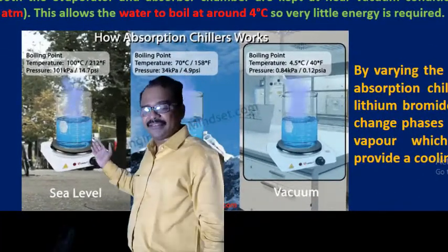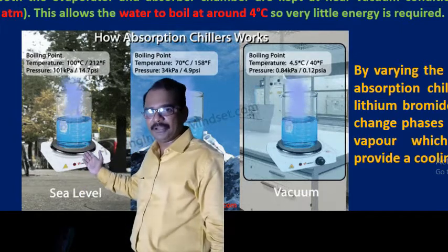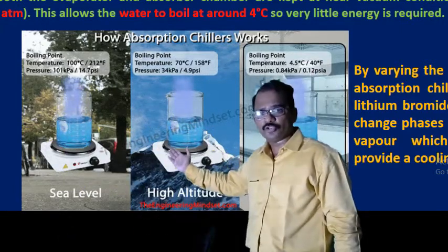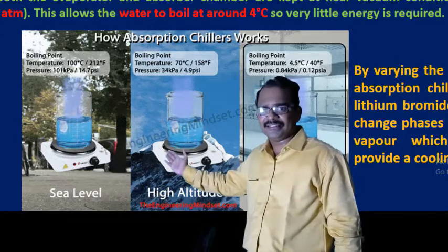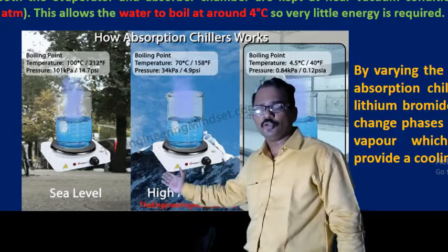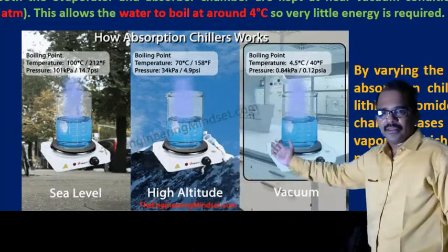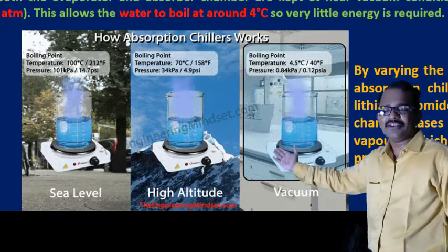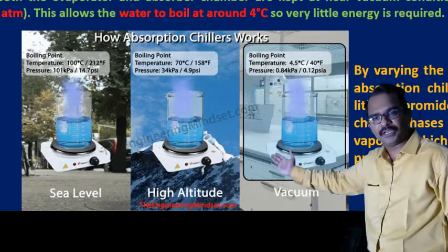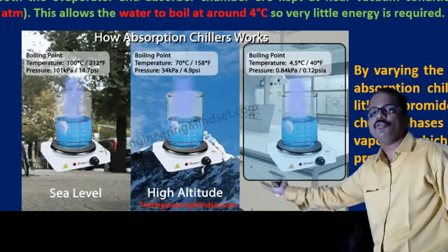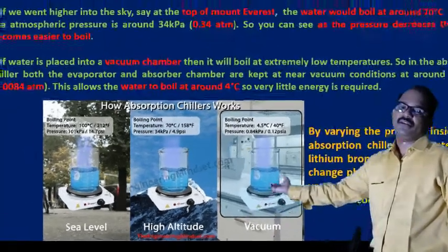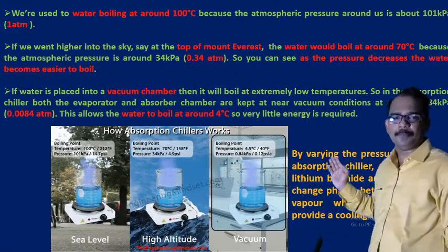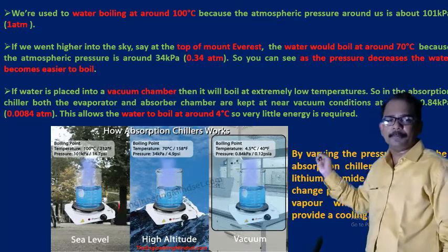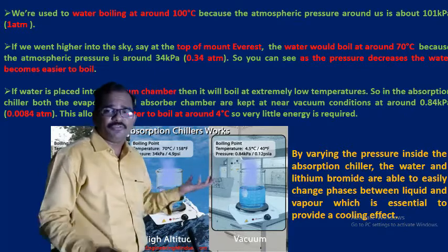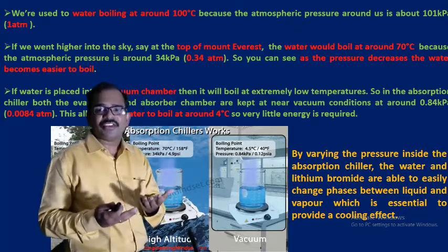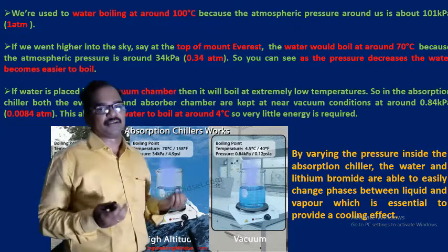You can see it here. At sea level, the boiling point of water is 100 degrees centigrade because the pressure is 1 atmosphere. At high altitudes, the boiling point of the water is 70 degrees centigrade because the pressure is reduced to 0.34 atmospheres. And in the vacuum chambers where the pressure is very low, at around 0.0084 atmospheres, you can see the boiling point is further reduced to 4.5 or 4 degrees centigrade. Therefore, by varying the pressure inside the absorption chiller, the water and lithium bromide used in it are able to easily change phases between liquid and vapor, which is essential to produce a cooling effect.